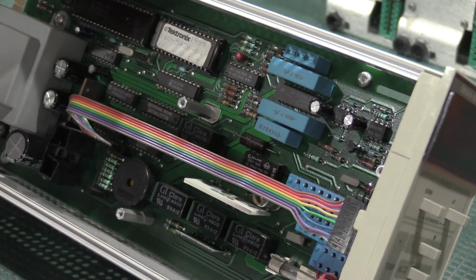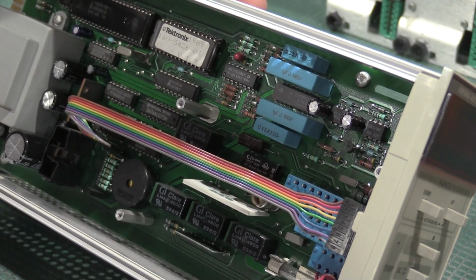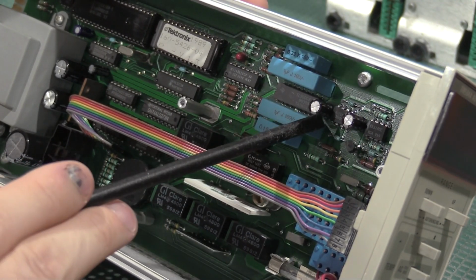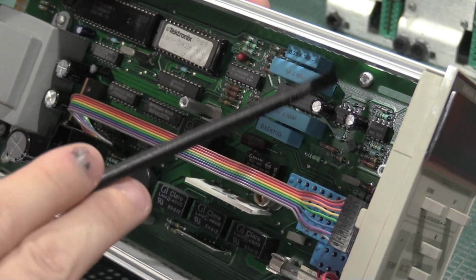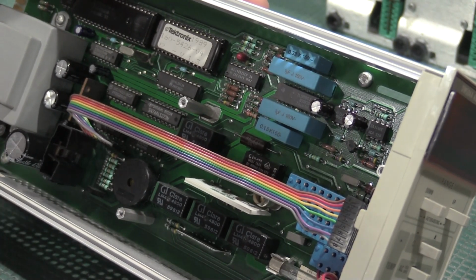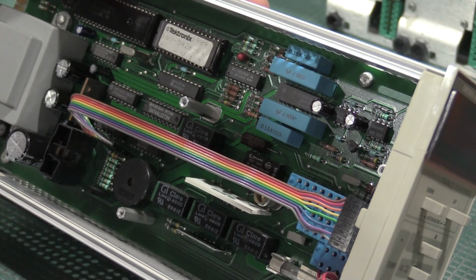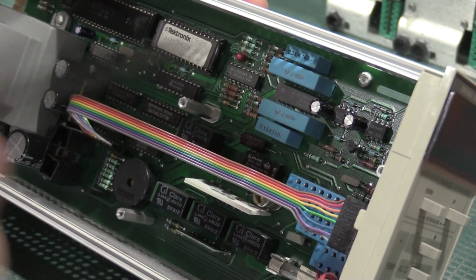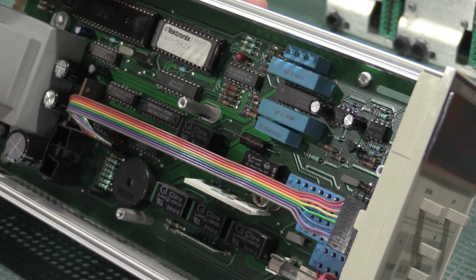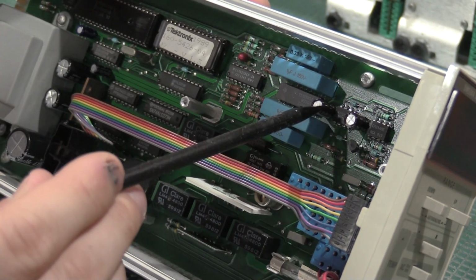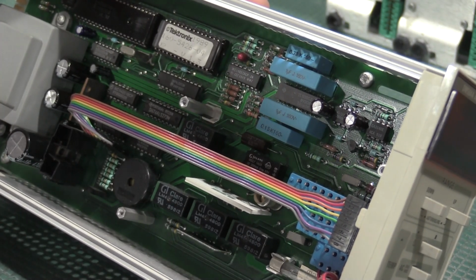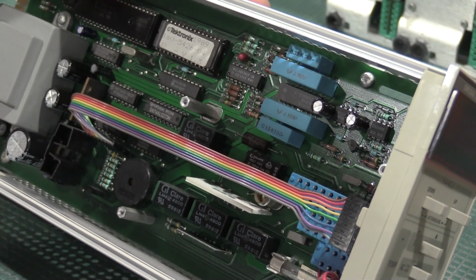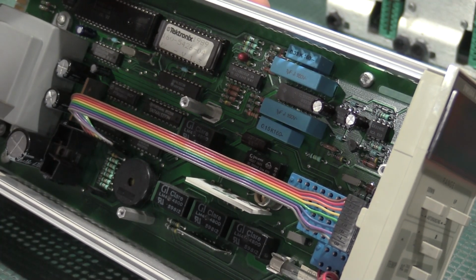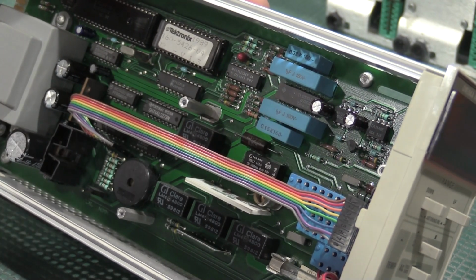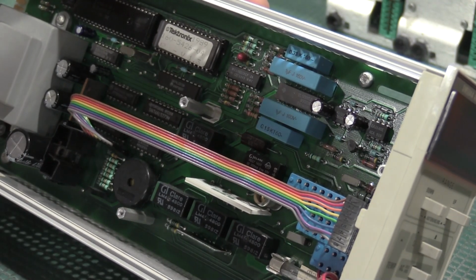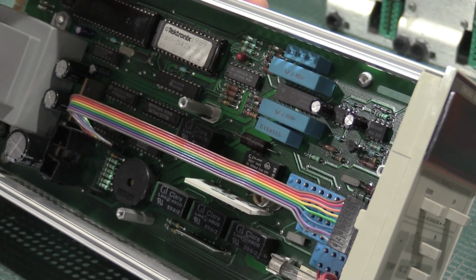Unfortunately for this repair, but fortunate for this unit's owner, if these two capacitors end up getting replaced, because they are in the ADC and they're part of the measurement circuit, a complete recalibration of this unit is necessary. So what I've got to do now is get the shields on. We'll see how well it measures now that we've got good components in it, knowing that these two caps were starting to fail. See how it measures and go from there. We do have all the test equipment here in the lab to get this thing all squared away. So that will be next on the list.